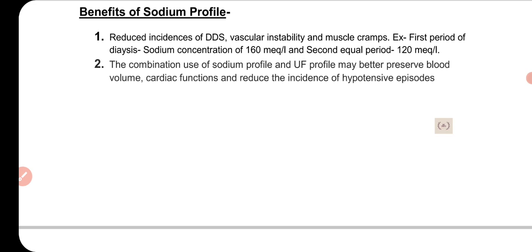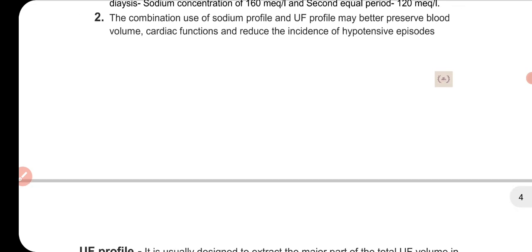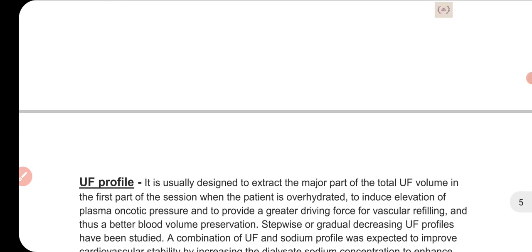Now the benefits of sodium profiling. Sodium profiling helps manage hypotension, dialysis disequilibrium syndrome, and muscle cramps. It reduces the incidence of dialysis disequilibrium syndrome and vascular instability. For example, in the first period of dialysis sodium concentration is 160 mEq/L and in the second period 120 mEq/L. With the decreasing profile, we can manage muscle cramps, vascular instability, hypotension, and dialysis disequilibrium syndrome. The combination of sodium profile and UF profile may better preserve blood volume, cardiac function, and reduce hypotensive episodes.